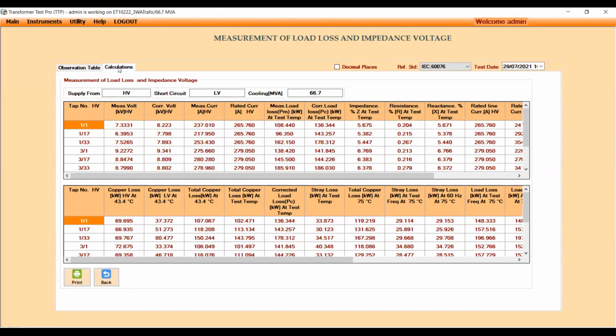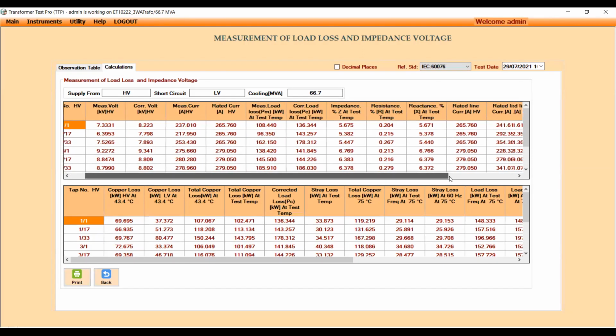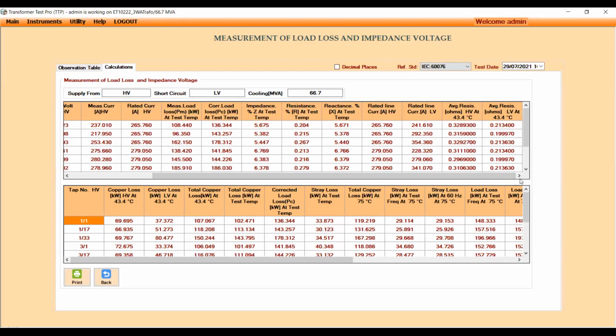Here you can see the supply from is the HV winding, the short circuit winding is LV, the cooling MVA is 66.7. Then the various tap numbers of the HV winding, the measured voltage, the corrected voltage, the measured current, rated current, the measured load loss, corrected load loss, the impedance at test temperature, resistance, reactance. And you can also see in the end where I scroll it down, you have all information related to average resistance for HV, LV, and then you have further information.